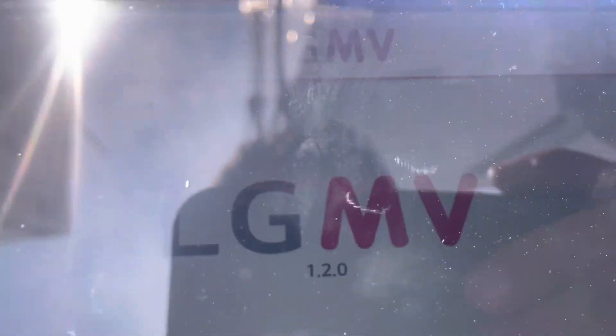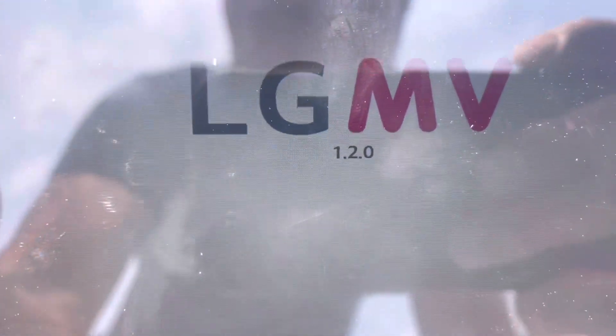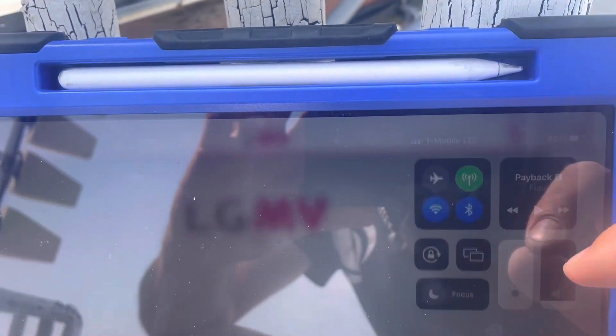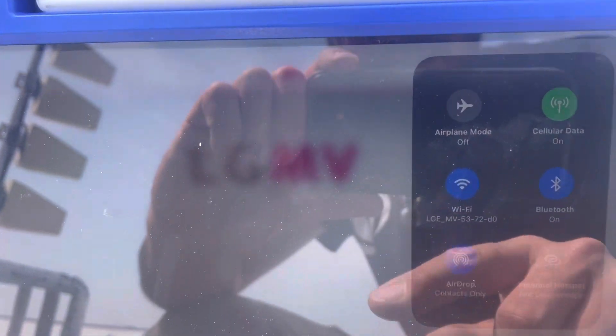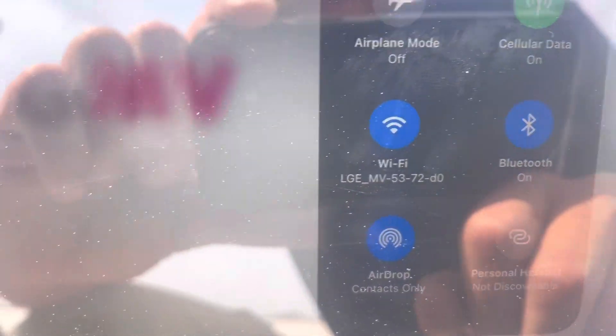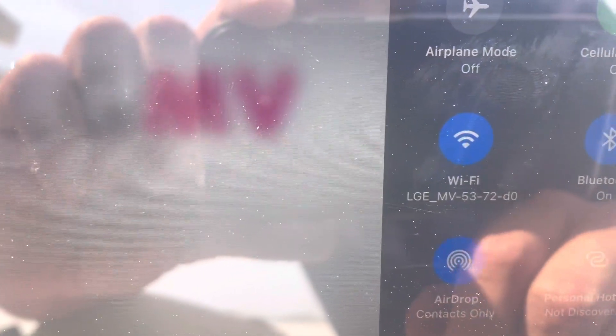What you're going to want is the LGMV app, and you want the latest version. As of April 6th the latest version is 1.2.0. What this thing does is create a Wi-Fi signal, so you want to go to your Wi-Fi, find it — mine's called LGMV 5372-D0 — and connect to it as if you were connecting to a regular Wi-Fi signal.